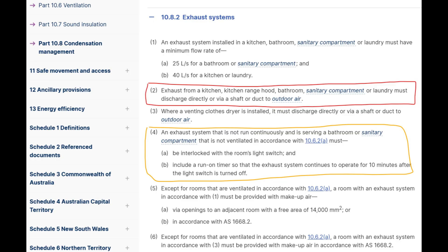In addition to this, there are minimum requirements for how much air has to be expelled. It's either 25 litres per second for bathrooms and toilets, or 40 litres per second for laundries and kitchens, because obviously these produce more steam.